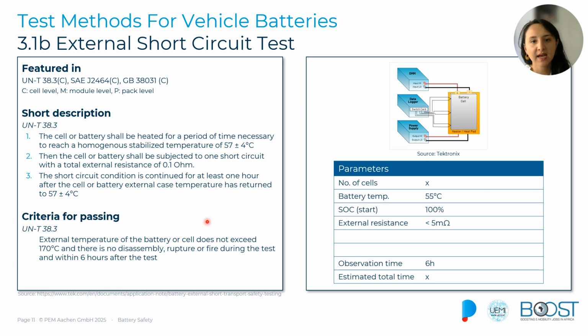the test. And this is going to be very important because external short circuits can happen in real life due to accidents, for instance crushing, due to damaged wiring or water ingress into the batteries. So the batteries passing this test will exhibit a robust design that can prevent the catastrophic events of a short circuit condition, that is very, very important for the BMS to handle.